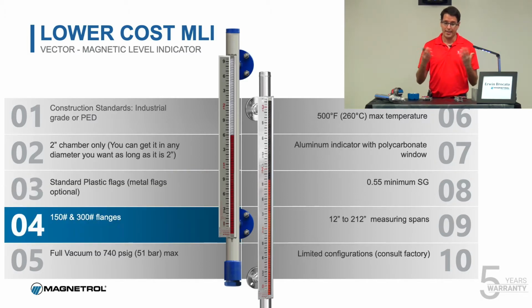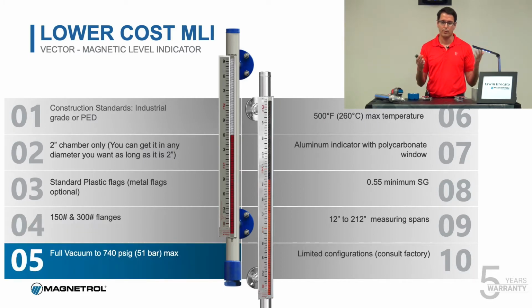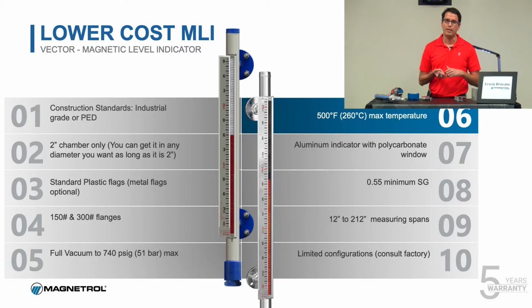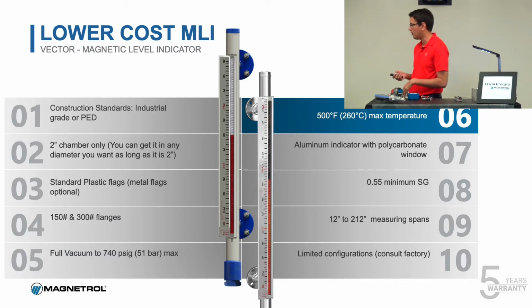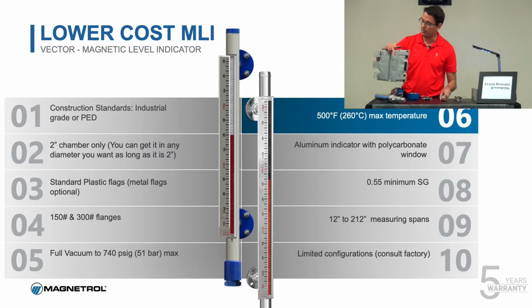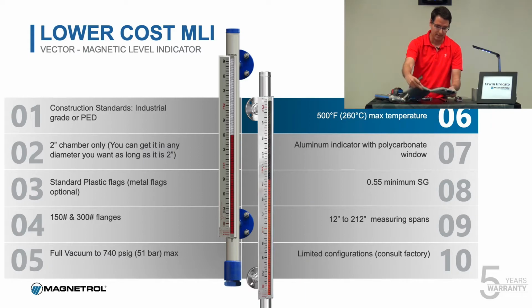Limit on the flanges. Low pressure for these devices. We cannot go beyond 300-pound flanges. Same thing with the pressure. 740 psi at room temperature is the limit on a 300-pound flange. And then the temperature, 500 F. It's actually a pretty reasonable temperature for one of these devices. And in that case, we're also going to use insulation blankets on the devices at those high temperatures. I'm just going to show it here a little bit, and y'all can see that. That's the insulation blanket on the device. Oh, it's over here. So we're not using the other camera. Good.